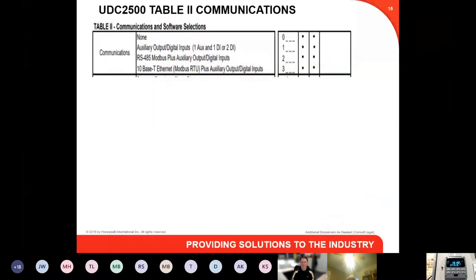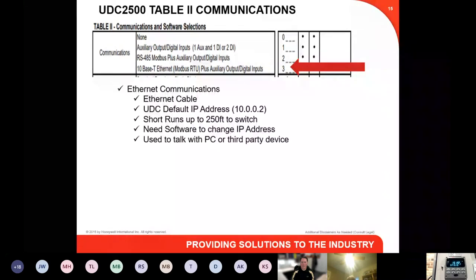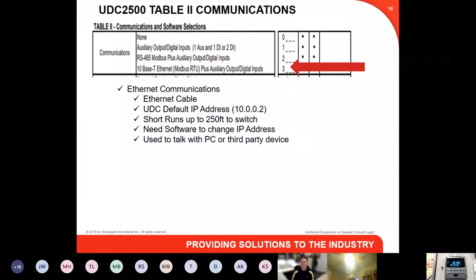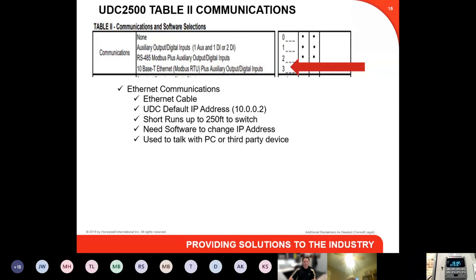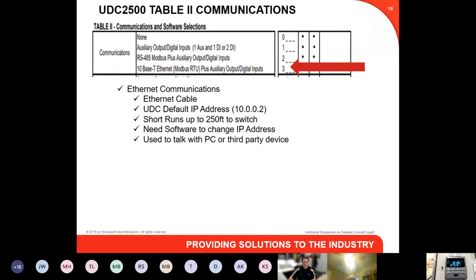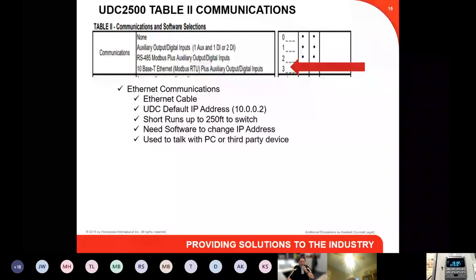Selection number three is the 10BaseT Ethernet, which comes with an RJ45 connection or straight terminal connection on the back of the UDC, allowing Ethernet Modbus communications using an IP address and Ethernet cable. You can access all the same parameters as with RS-485 Modbus — this is called Modbus RTU utilizing Ethernet. The maximum first-run distance from the UDC to the plant network is about 250 feet; beyond that, you need a hub or switch.